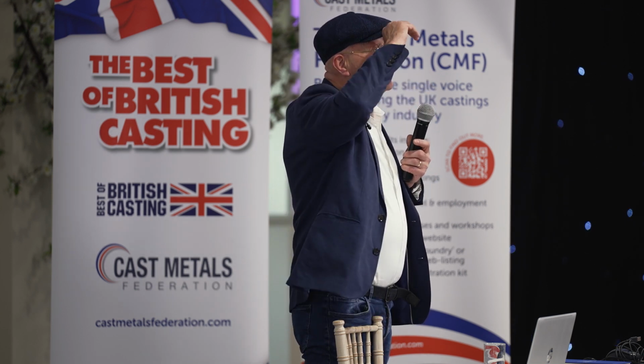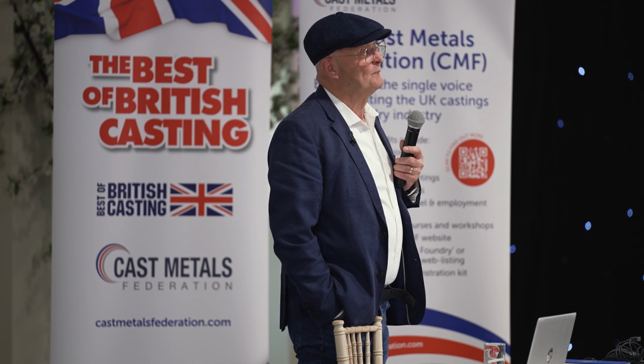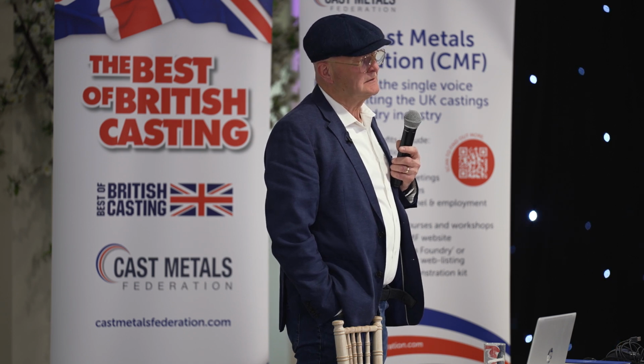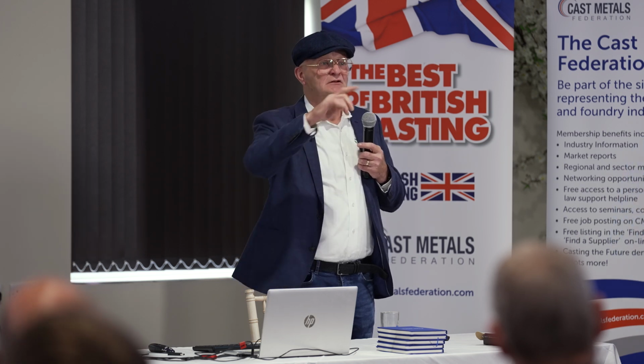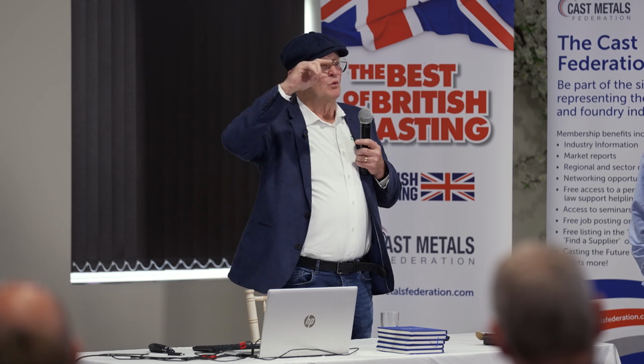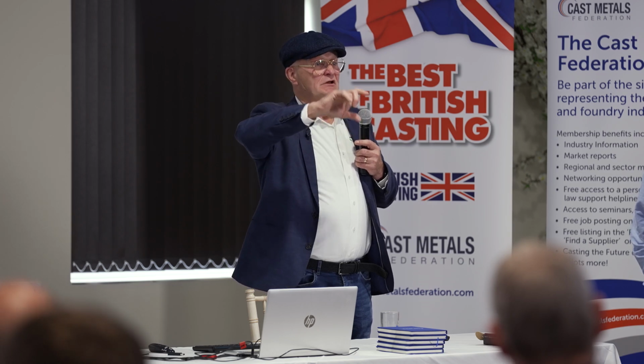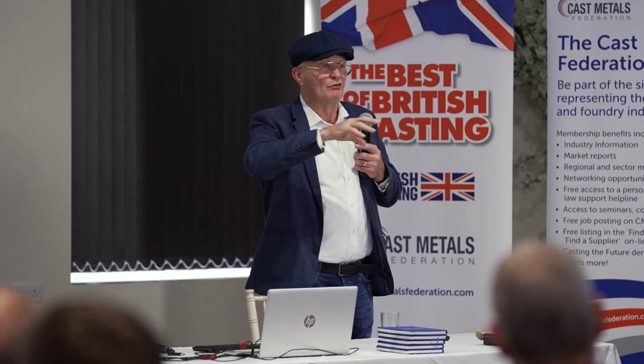Yes, sir. The refractory will probably be because in normal applications, they try to get the temperature, you've got an oxidizing flame, right? Yeah. Because some of the refractories contain silica or silicon, it'll oxidize. If you've got some carbides in there, it'll oxidize. In your case, you won't get the oxidation. No. That's one of the big things about it, particularly, as I say, scale. That furnace that I showed you the top hat on, when they had those shafts from the mining, it was from ABB, making electric motors, and they had a process where they actually shot blast them and then put them on a lathe, and there was over $90,000 a month in tooling costs they didn't need to touch, which was just an incidental saving on their processing.